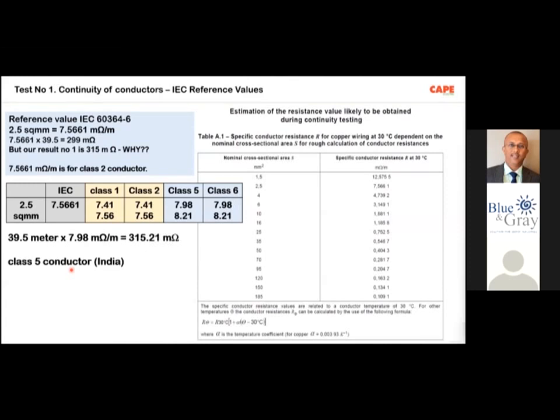Means the copper must have a very less resistance in comparison, about 8 to 9% lesser resistance. Actually, world over, class 2 copper wires are used for wiring in a building, whereas in India, sometimes class 2 copper wires are not available in the market. If you have any doubt, you can check with your wire supplier, you call them and find out whether they have class 2 copper wire in their stock.